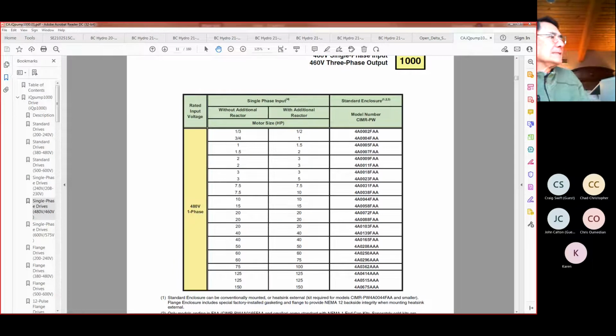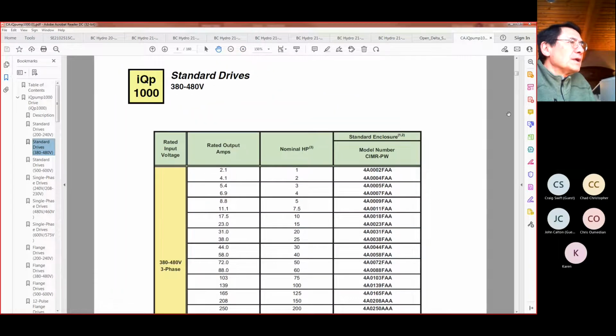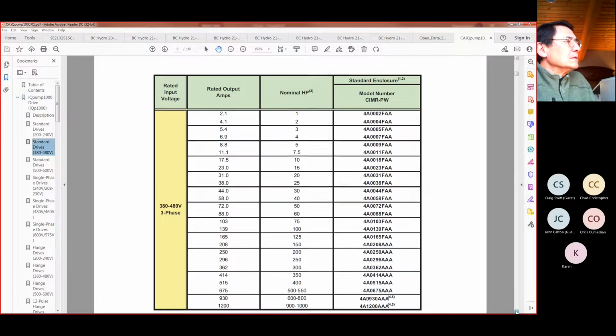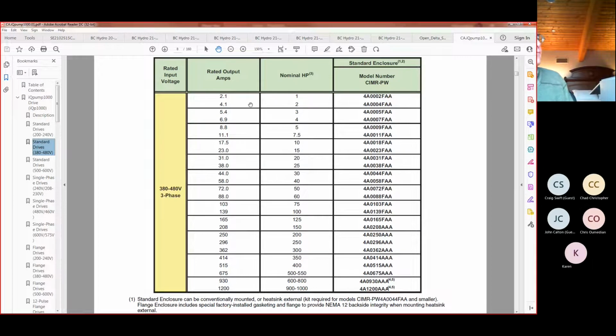one frame size. So if I'm looking here at the iQp 1000 catalog, and you can see that here at the 380, 480 volts, so for us 480 volt US voltage model line, we have different output amp ratings, which result in different part numbers, but these heavy lines indicate a frame size change. What that frame size does is when we go from 2.1 to 4.1 amps, the frame doesn't change. Therefore, the capacitors in those two models are the same. We're looking for increased capacitance because an open delta system increases the voltage variance, the voltage ripple on the DC bus. Therefore, we want more capacitance. So we need to go across the line.